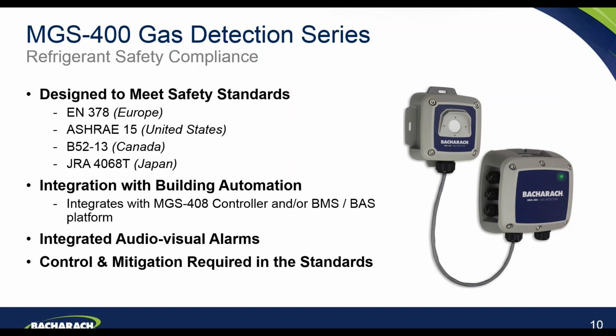It fully integrates with building automation, so you can either integrate the detectors into the 408 controller or on-site BMS systems. Each of the detectors, whether it's the 410, the MGS-450 or the MGS-460, all come with fully integrated audio and visual alarms. And the performance and design of the units is such that it ensures the control and mitigation requirements are met as per the standards.